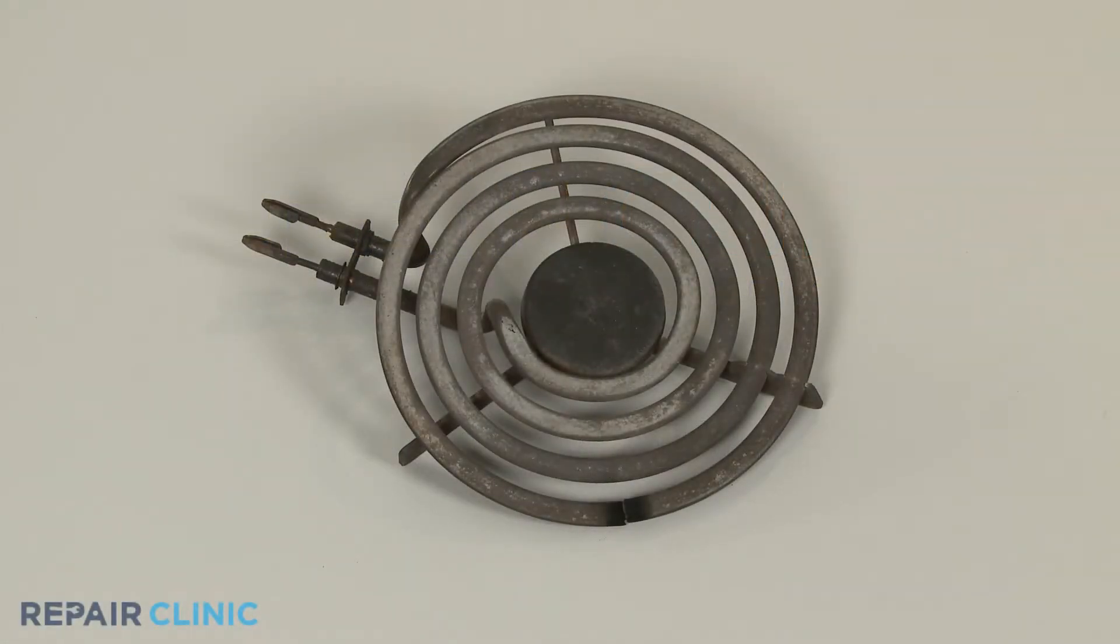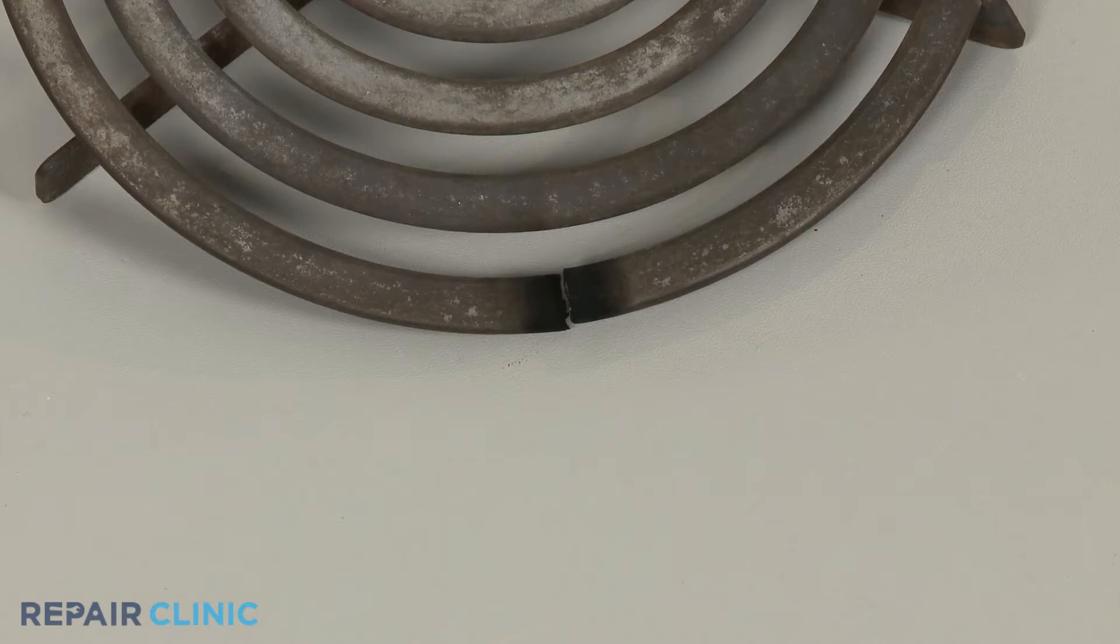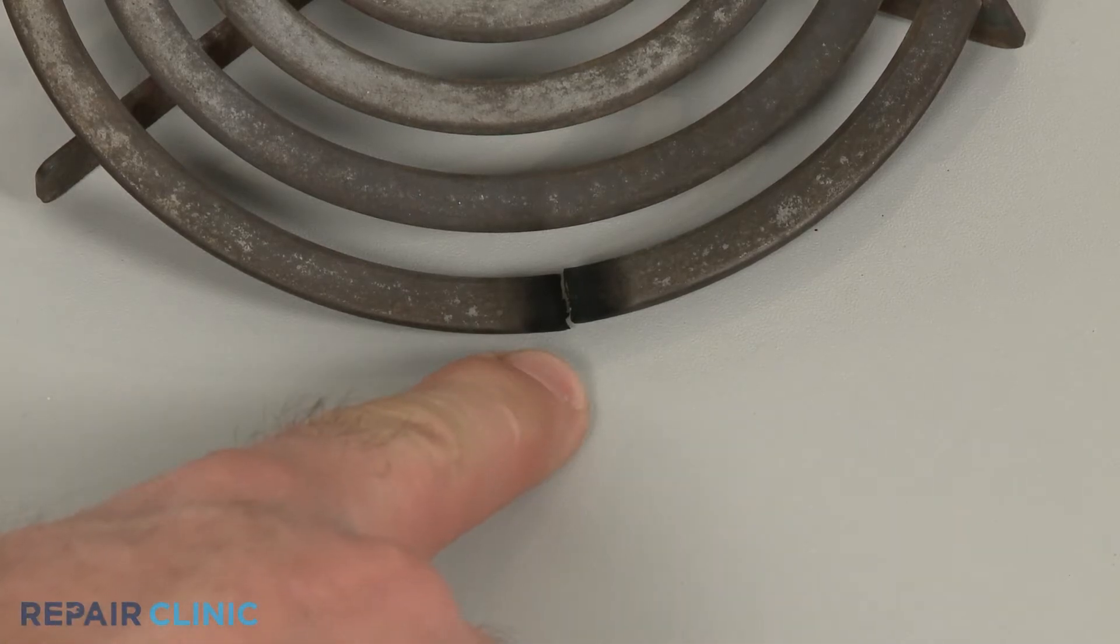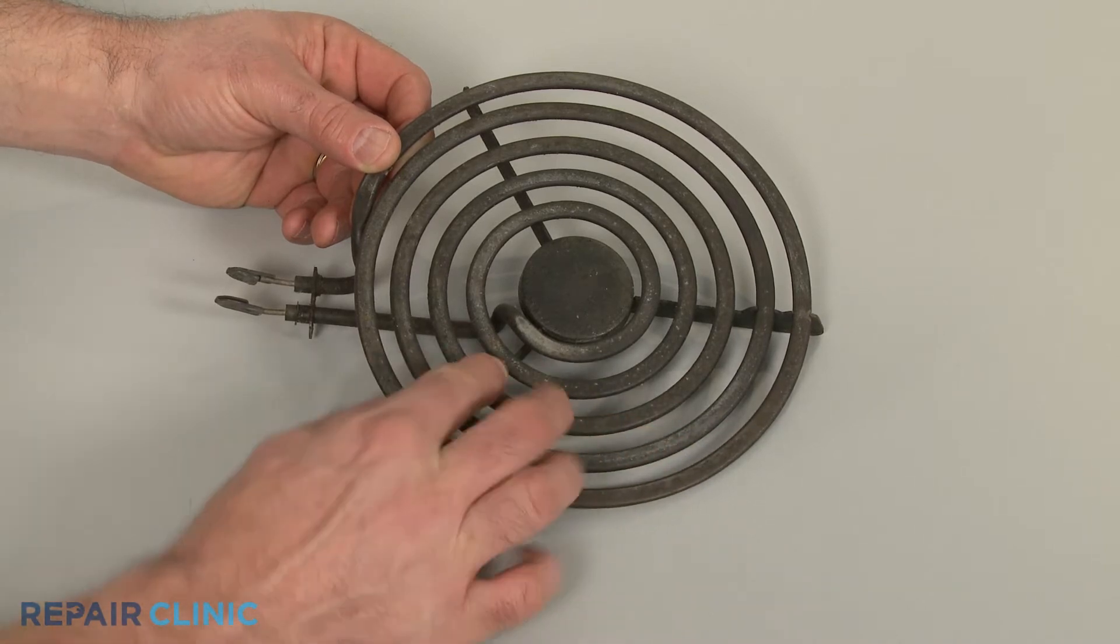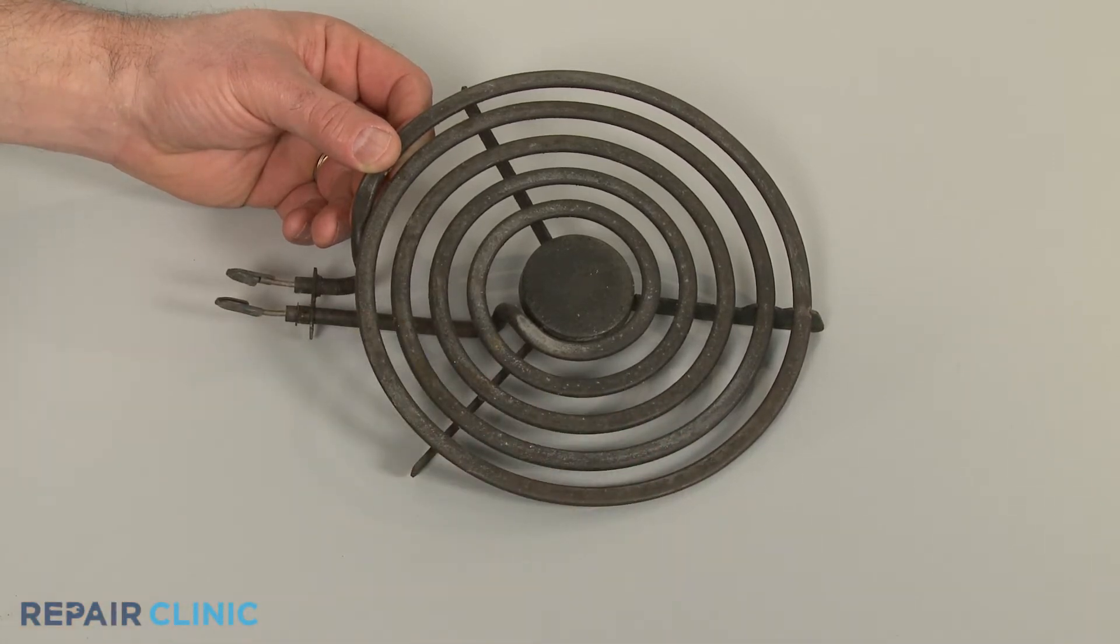You can often determine that a surface coil element is burned out by simply checking to see if the element is visibly broken or blistering. But since you can't always tell by looking, it's best to perform a continuity test.